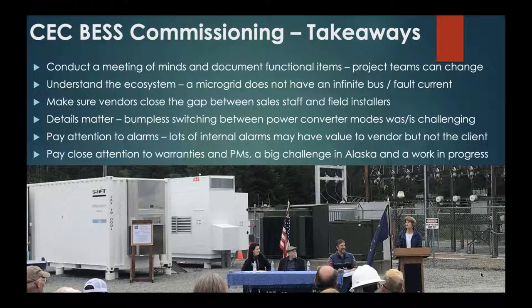We did have some challenges. The details really matter. When you're balancing a grid, the bumpless switching between different modes of operation still isn't truly bumpless, but it's adequate and functional. It turns out that when you switch modes, you have to pretty much power down and power back up very quickly, and that doesn't work well when you're balancing frequency.